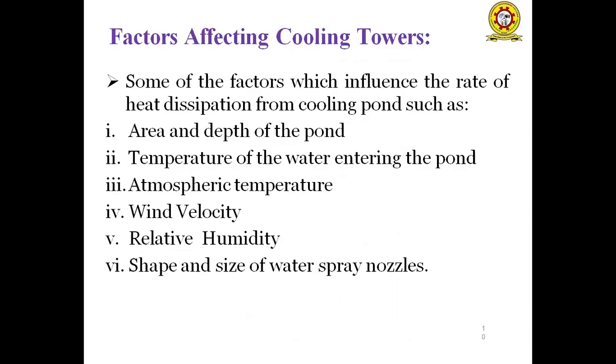Next, factors affecting cooling towers. Some of the factors which influence the rate of heat dissipation from the cooling ponds depend upon the area and depth of the pond, temperature of the water entering into the pond, atmospheric temperature, wind velocity, relative humidity, and shape and size of the cooling water nozzles.